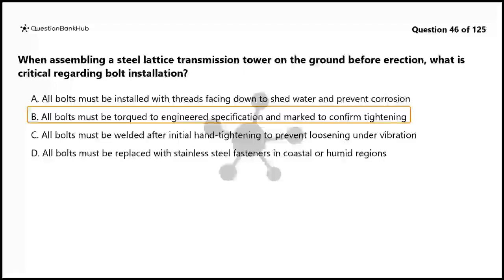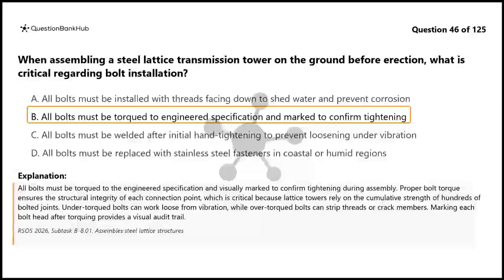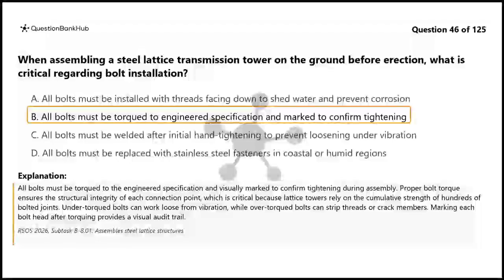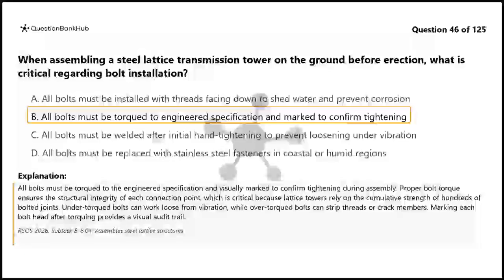The correct answer is B. All bolts must be torqued to the engineered specification and visually marked to confirm tightening during assembly. Proper bolt torque ensures the structural integrity of each connection point, which is critical because lattice towers rely on the cumulative strength of hundreds of bolted joints. Under-torqued bolts can work loose from vibration, while over-torqued bolts can strip threads or crack members. Marking each bolt head after torquing provides a visual audit trail.